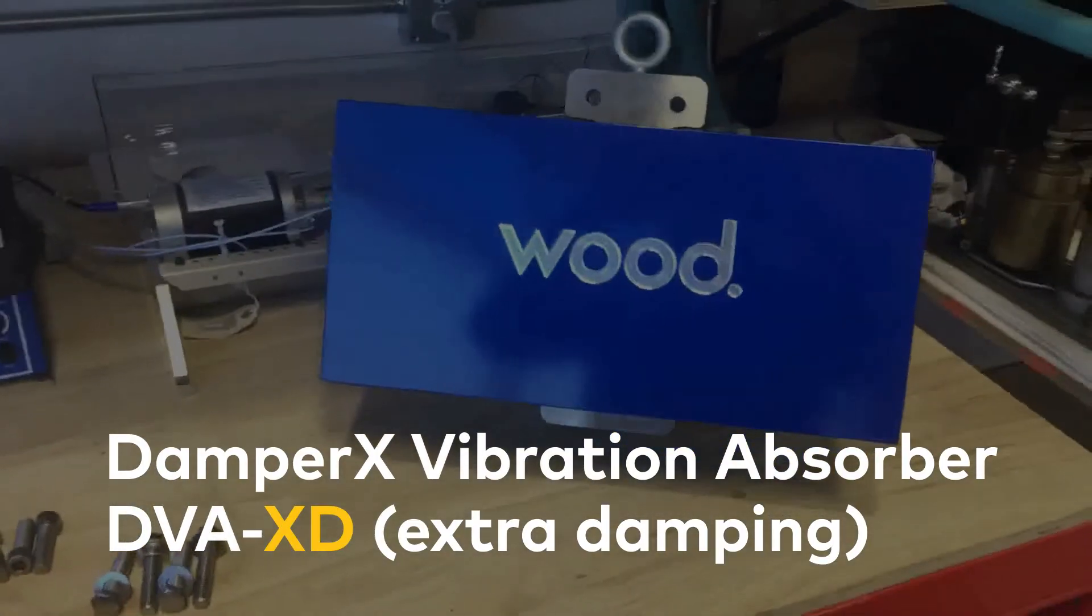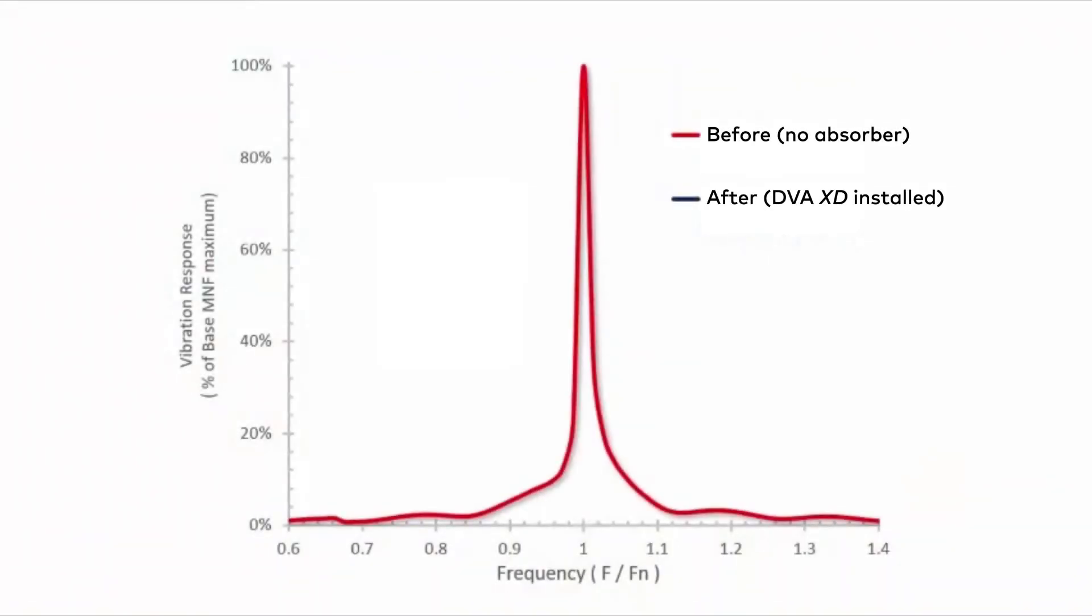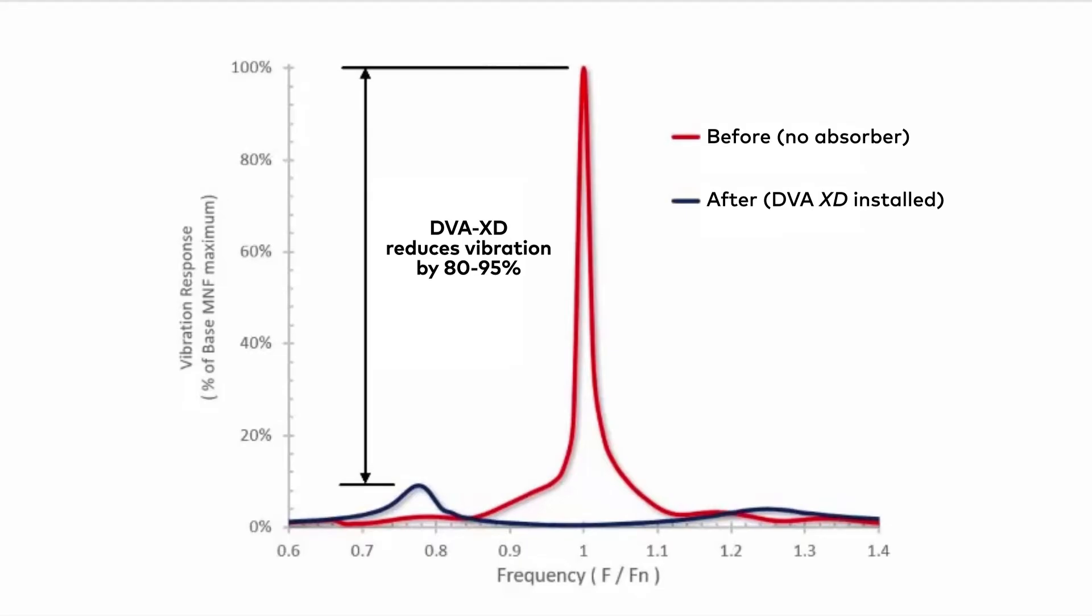So meet Woods newest addition to the DVA lineup, the DVA XD. This is the highest damped version of our DVA and typically produces a reduction of 80 to 90 percent from base levels. That means the DVA XD can take on even the most challenging vibration problems.